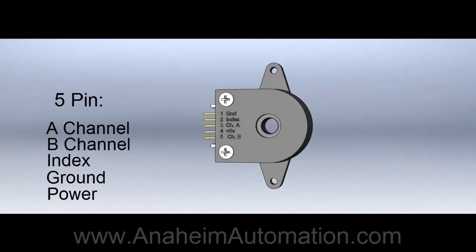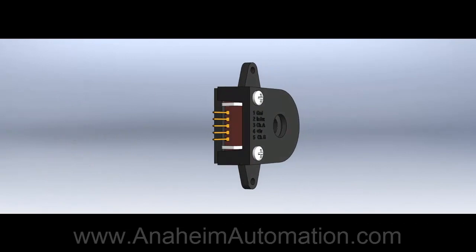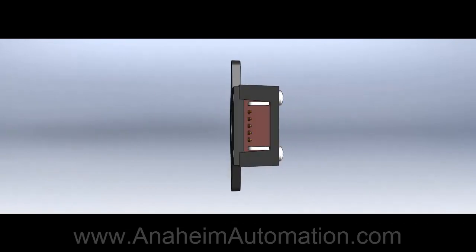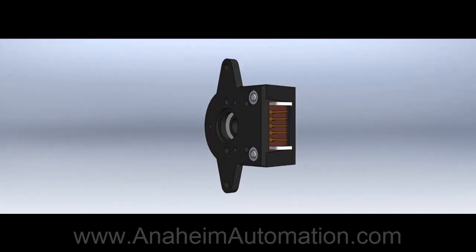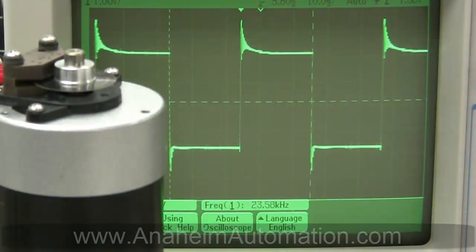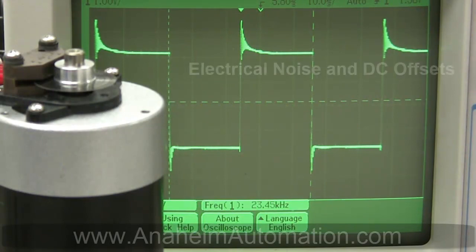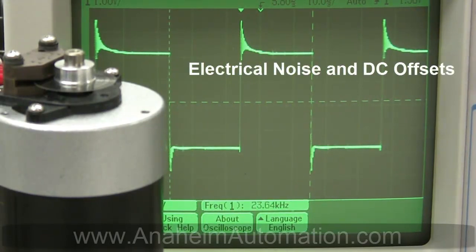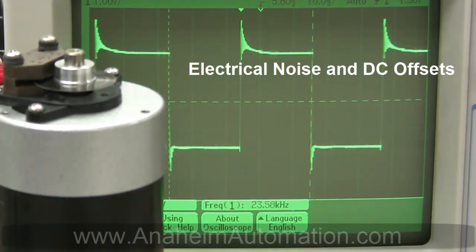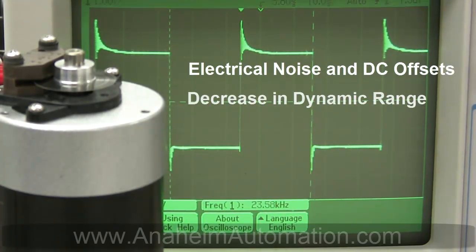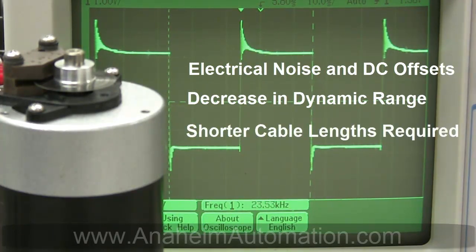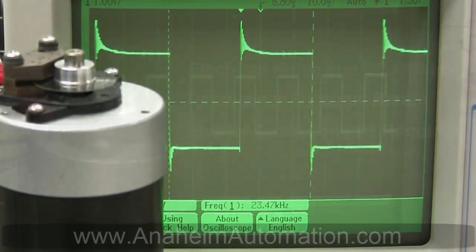For multi-channel systems, the ground pin is shared among all other input pins. Due to these characteristics, single-ended encoders are more susceptible to electrical noise and DC offsets. These interferences decrease the dynamic range of the input signal, therefore requiring single-ended encoders to utilize shorter cable lengths of 6 feet or under.